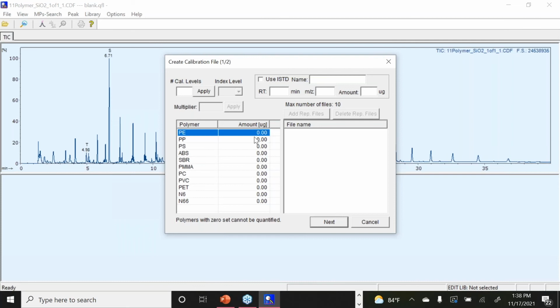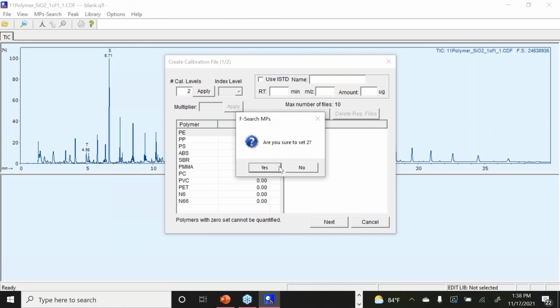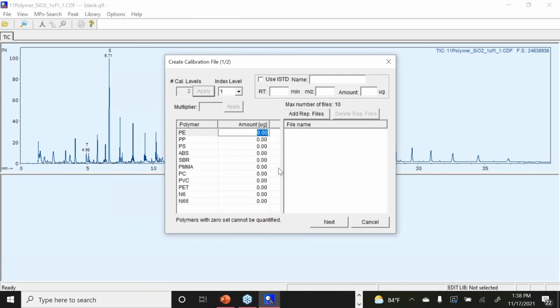So, okay, good point. Before I can enter the amount here, I forgot this step: you need to enter your calibration level. In this case, I'm doing a 2-point calibration, so I say 2, apply. Are you sure you want to set it as 2? You would say yes. And now it allows me to change the amount based on my first calibration standard, which was 4 milligrams, and the amount of PE is 160.